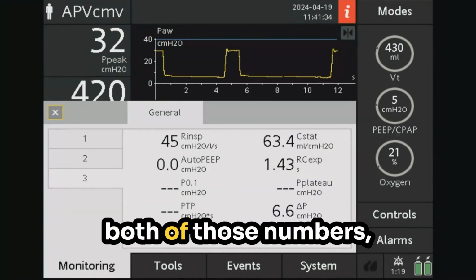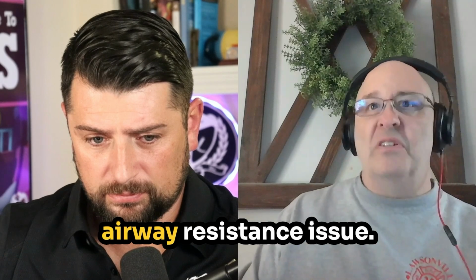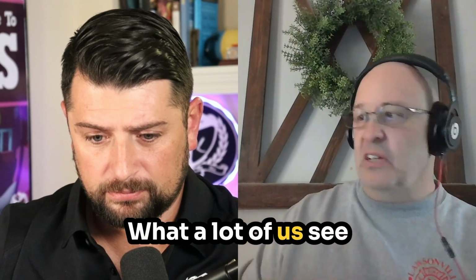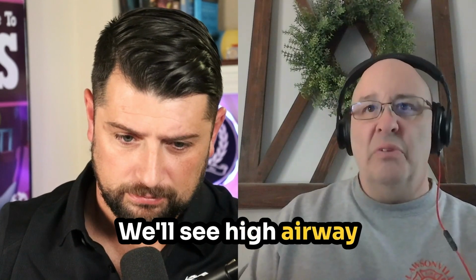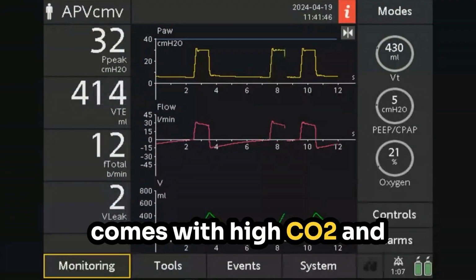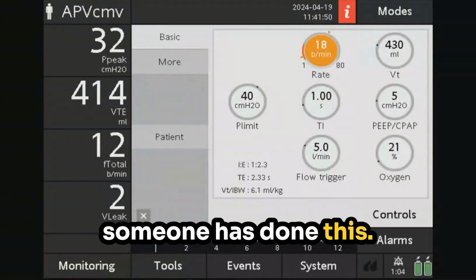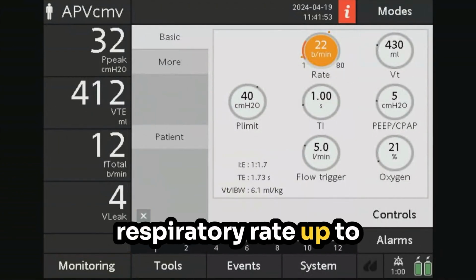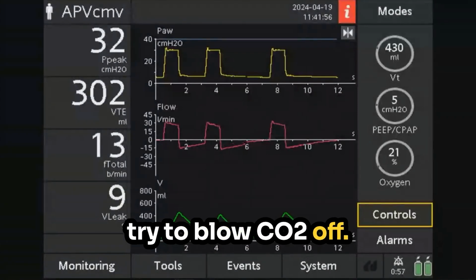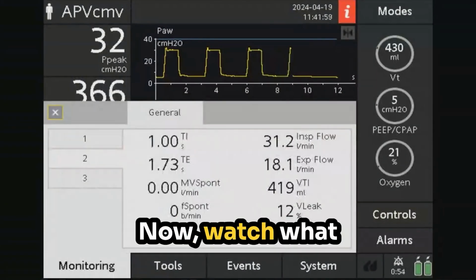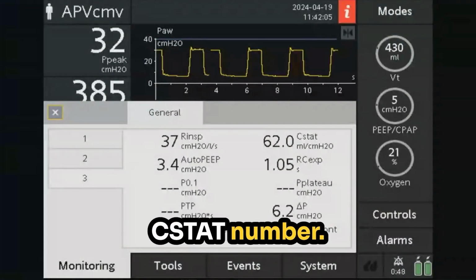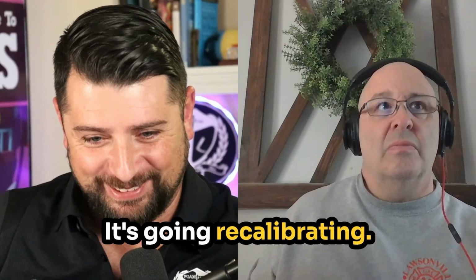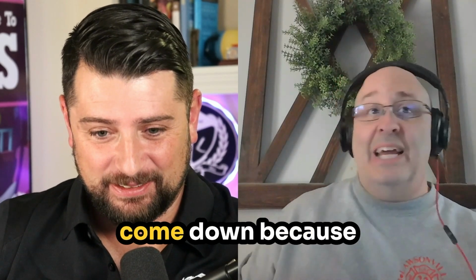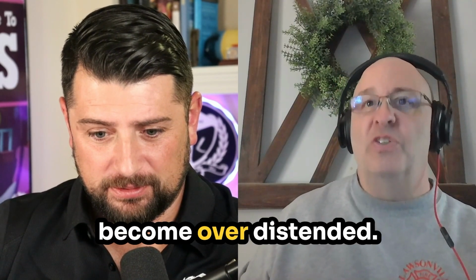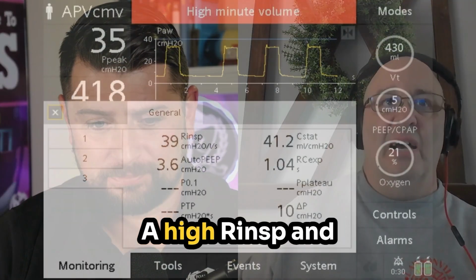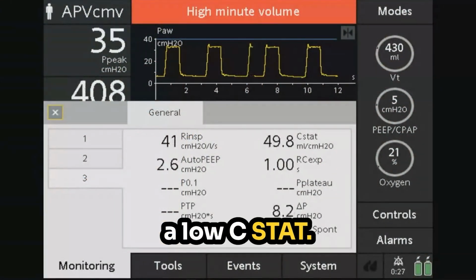So in this case, looking at both of those numbers, you could say it's really an airway resistance issue. What a lot of us see on the clinical side is high airway resistance, and that comes with high CO2. And someone has done this. They've turned the respiratory rate up to try to blow CO2 off. Now, watch what happens to your C-stat number. It's recalibrating. You're going to watch it start to come down, because at some point your patient's going to become over-distended. And you'll see a high R-insp and a low C-stat.